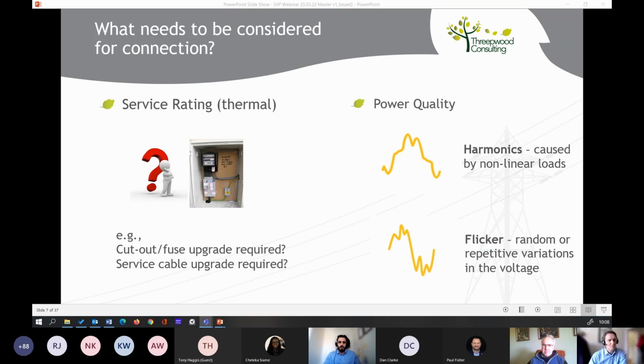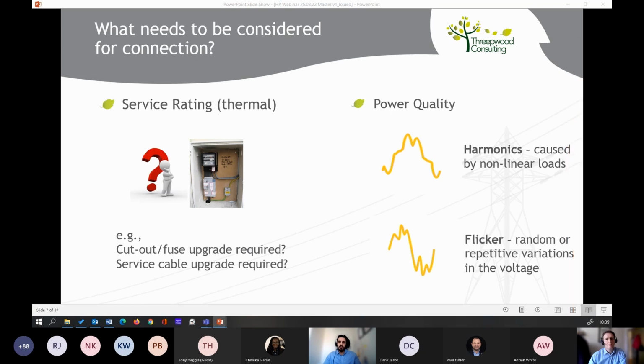The other factor we've got to look at is power quality - what I mean is harmonics. Harmonics will cause equipment to heat a lot more because the sine wave is not a full sine wave, so we've got to be careful of that. It's inherently present in power electronic components, which heat pumps have. But also flicker, because once you're switching in a large 3, 6, 9 kilowatt load, that's going to have an impact on the network.